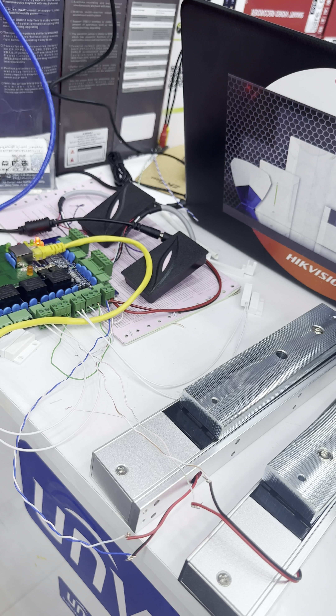After that we need to do the settings. Okay, when the panel is installed, this function is not showing here. Okay, only control and department personal access privilege. Anti-passback and interlock system you have to add from here. Tools, from extend function, the password is 5678. Okay, after that the window will open. Okay, configuration, you have to activate anti-passback and activate interlock. If you need other options, you can check them here, and please tick.